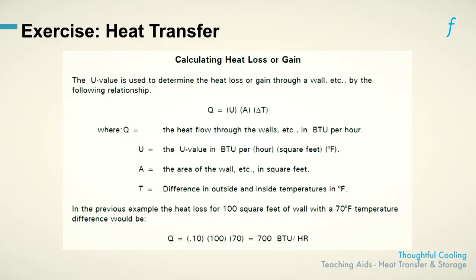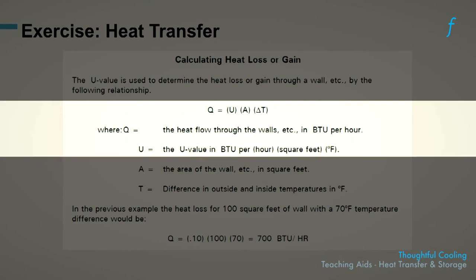So this equation here, which is the conduction heat equation, allows one to calculate the Q as a function of the U value, which is now reduced. As we increase the thickness, the resistance has increased, or the conductance has come down for the same amount of area and for the same amount of delta temperature. So essentially what we're doing is we're saying, let me reduce the U but increase the embodied energy. And what we've often seen is that the reduction of the U is applicable for the entire life of the building, right? That wall exists for, say, decades, 20, 30 years. We get the benefit of reduced U for a very, very long period of time for the increased expenditure of embodied energy once at the construction stage. Nonetheless, this is a very methodical and rational way of doing the assessment.